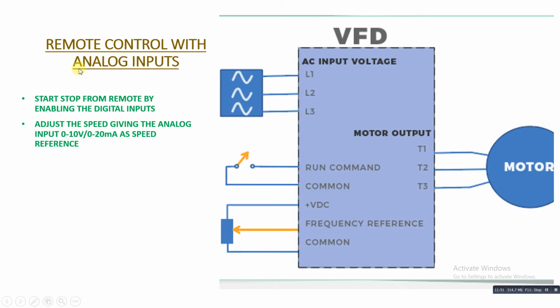And remote control with analog inputs. The same way, you start and stop the VFDs by enabling the digital inputs. As I told you, you can give the run command with the digital inputs by enabling this. But for speed reference you can give external analog inputs like 0 to 10 volt or 0 to 20 milliampere, whatever the analog signals available from an external source like PLC or BMS. By giving these analog inputs you can increase or decrease the speed of the drive. This is one of the main ways people are using around the world.